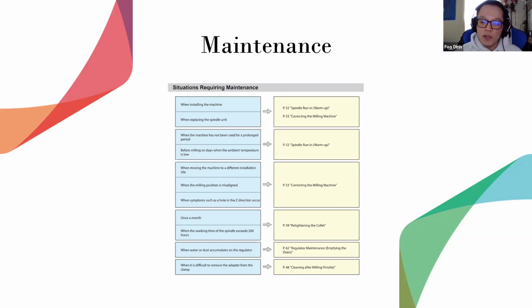We always want to do that anytime we do anything with a collet. Okay. Any little shift or adjustment that may or may not occur while doing the collet maintenance will affect the calibration of the mill. Okay. So the collet maintenance in turn runs with the calibration once a month or every 200 hours, whichever comes first.